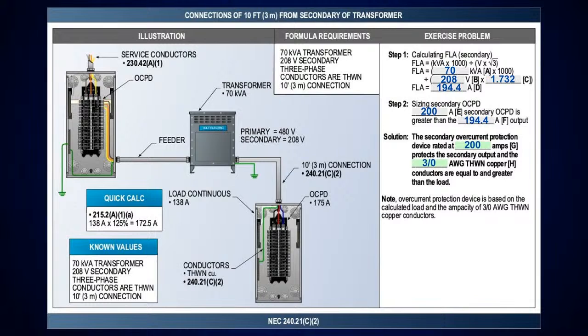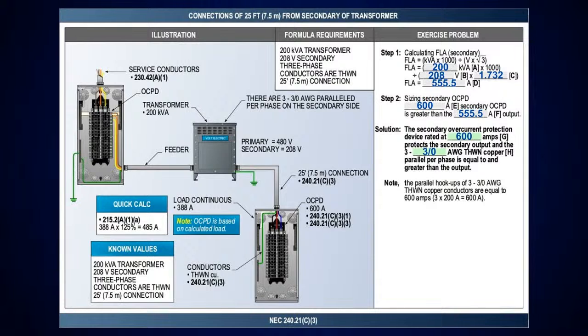And this is kind of interesting too. I kind of wanted to ask you this question. If you were to have that on the exterior of the building, what would be the limit of the tap conductor? There ain't no limit. And we'll get to the outside transformer conductors here in a minute. And we'll show that calculation. They're all the same calculation.